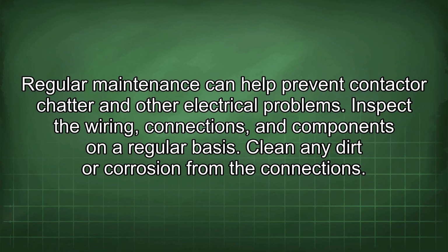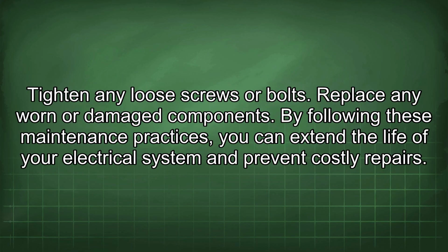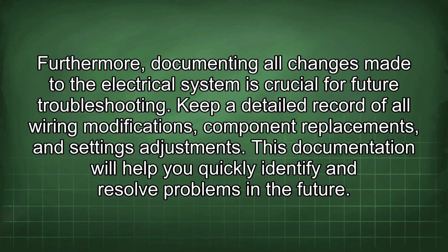Regular maintenance can help prevent contactor chatter and other electrical problems. Inspect the wiring, connections, and components on a regular basis. Clean any dirt or corrosion from the connections. Tighten any loose screws or bolts. Replace any worn or damaged components. By following these maintenance practices, you can extend the life of your electrical system and prevent costly repairs. Furthermore, documenting all changes made to the electrical system is crucial for future troubleshooting. Keep a detailed record of all wiring modifications, component replacements, and settings adjustments. This documentation will help you quickly identify and resolve problems in the future.